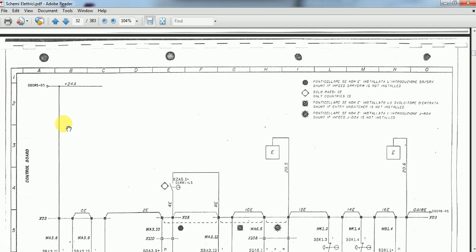Now, if I'm talking about this PLC input, how can I describe its location in the diagram? It's H3. Another thing which is very important is the wire route. It's the wire number, and you can see that it's going upward. And just here you can see the arrow which shows that the 24 volts are coming from here.